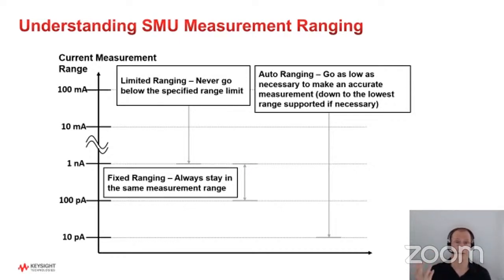So there are actually 3 basic types of measurement ranging. There's fixed ranging, where the measurement range always stays in the same range. There's limited ranging, which starts at the top of the range and then goes down to whatever limit you've specified. It won't go any lower than that. And then there's auto ranging, which will go as low as necessary to make whatever measurement you need to make. In terms of speed, the fastest is fixed ranging, next fastest is limited ranging, and then after that is auto ranging. So it's important to understand when you might want to use each type of ranging for the different measurements you're making.